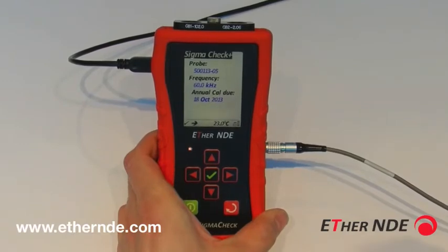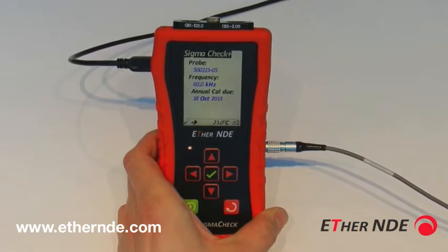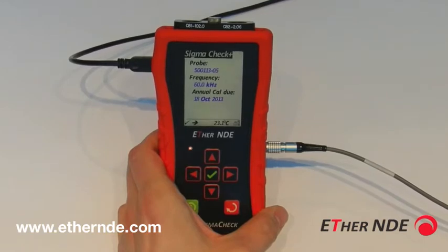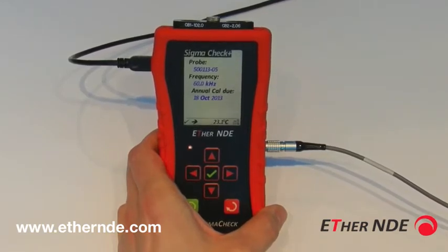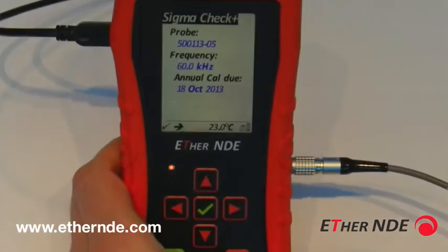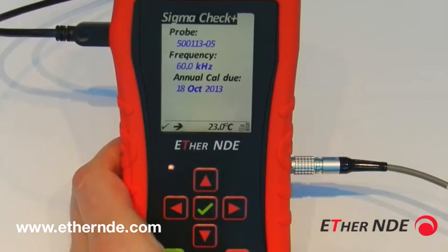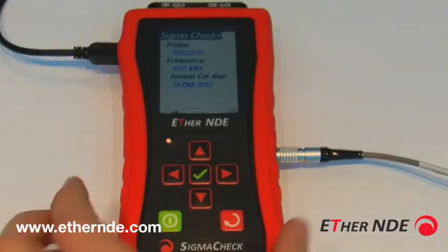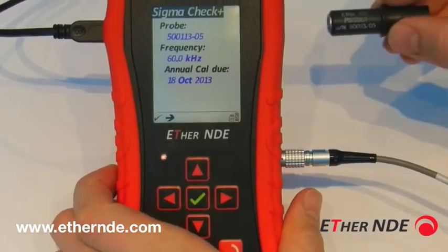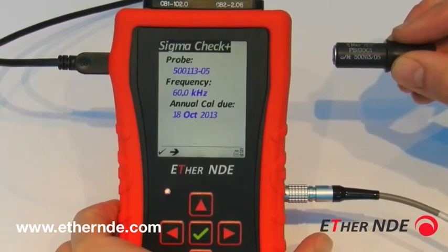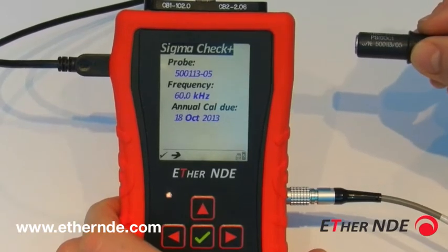Using the Sigma check menu system to configure the basic operation. As you can see, we are currently on the home screen. The probe ID is shown, the current frequency of the instrument, and when the annual calibration is due. When using a Sigma check, every probe is characterized — it's very important to have the correct probe shown. The probe ID here, 500113 05, is selected, and the current desired frequency, 60 kilohertz, is selected.